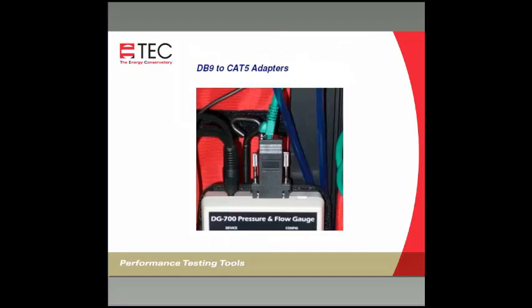The other way of doing it is to connect using the serial port on top with these little adapters that allow you to convert that serial into Cat5, and then we can use Cat5 cable. The beauty of that is, on a large building test, that Cat5 cable can run 3,000 to 4,000 feet and it's a rock solid connection that's not going to drop out on you.